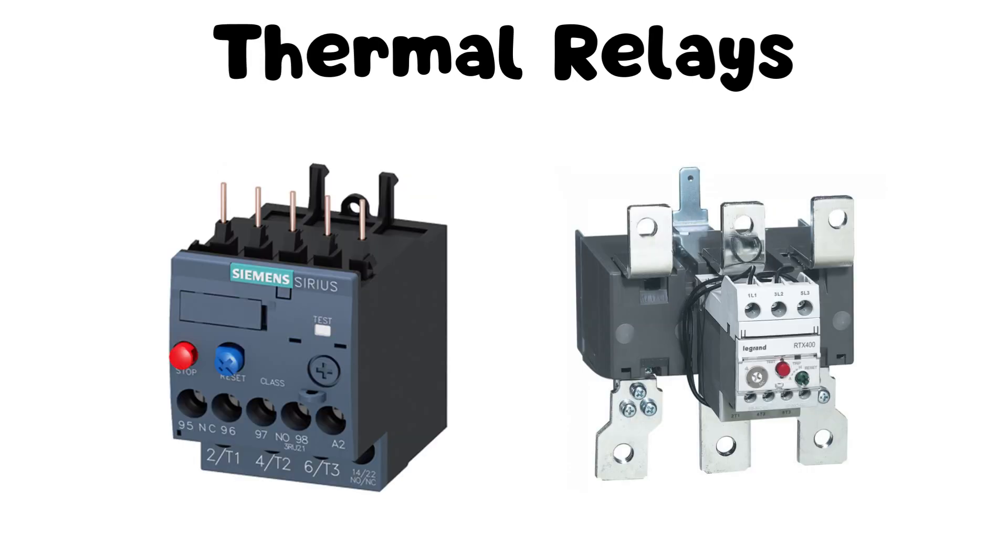Thermal relays: Thermal relays are designed to protect motors and other equipment from overcurrent conditions. They use a bimetallic strip or a heating element that expands or contracts based on the current flowing through it. When the current exceeds a predetermined threshold, the bimetallic strip bends or the heating element triggers a trip mechanism, which interrupts the circuit and protects the equipment.